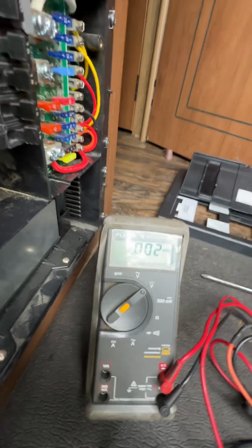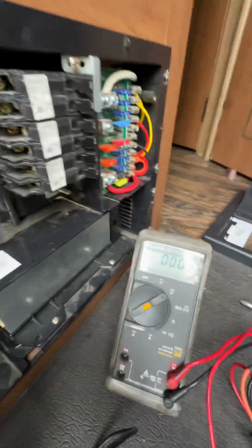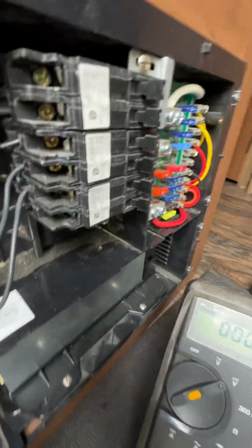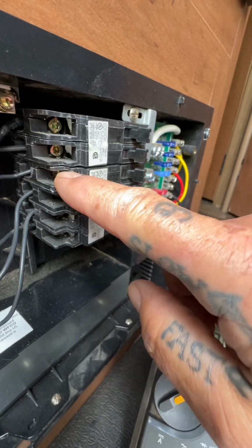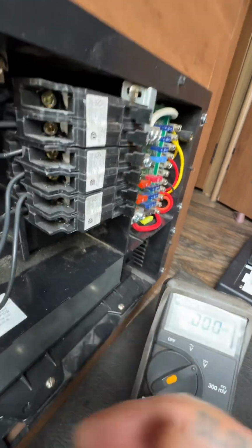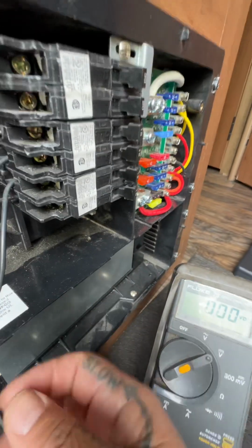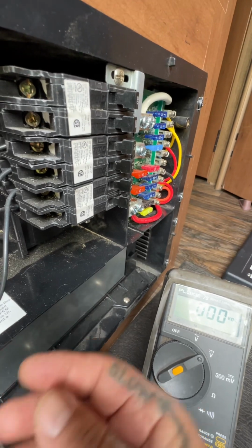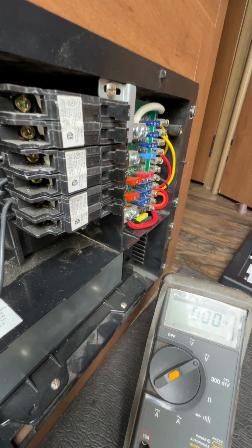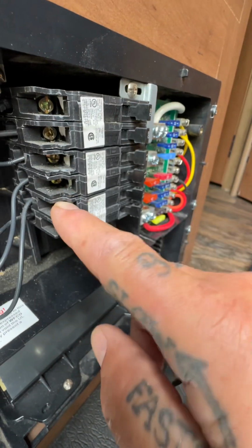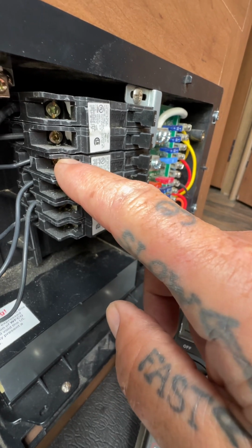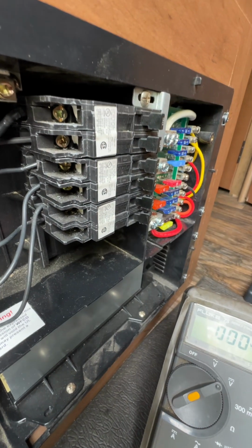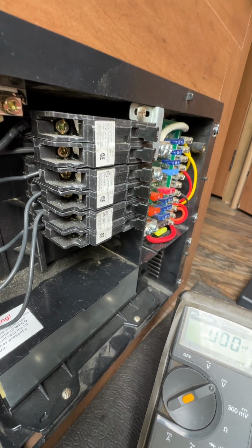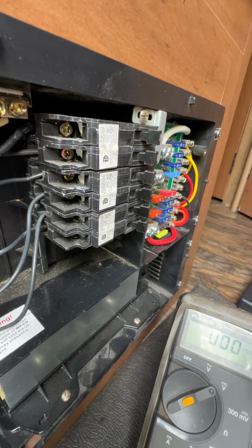So what I'm trying to say is: test to make sure you have power coming in from your circuit breaker in this wire. Leave those wires you had connected, disconnected, connected back up, so you can check live circuits. Check your power from here to make sure you're actually getting it, because you showed me in your picture that you're getting power from your pedestal.